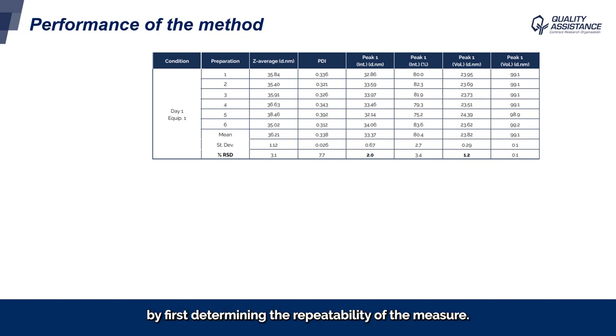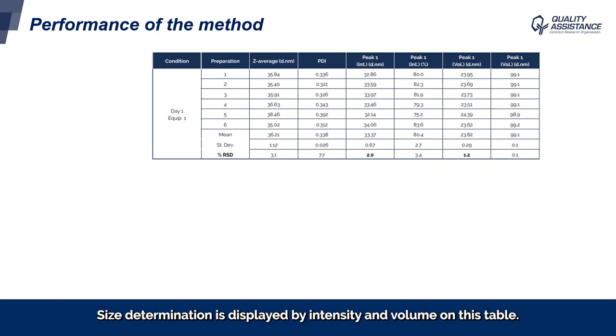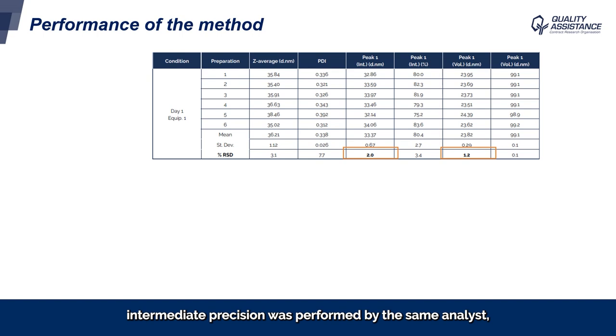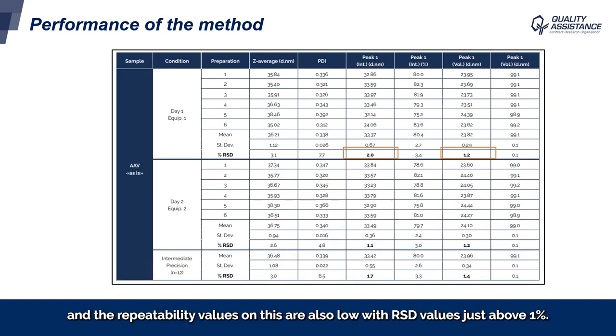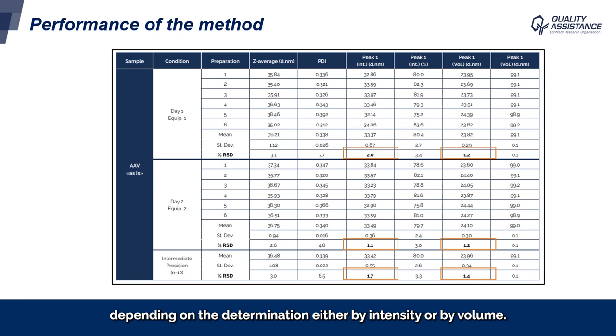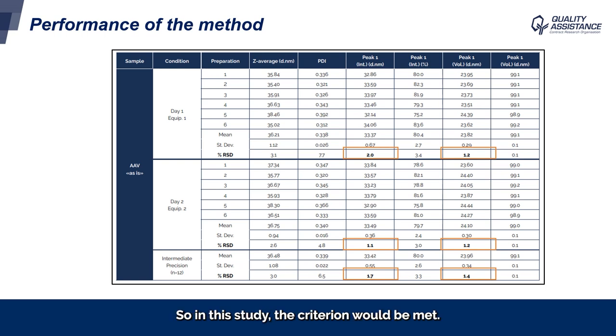Finally, we checked the performance of the method by first determining the repeatability. For one day on one equipment, the measurement was performed six times. Size determination is displayed by intensity and volume on this table. Circled in orange, we see low RSD values of 2% or 1.2% for determination by intensity or by volume. Intermediate precision was performed by the same analyst but on a second equipment and on a second day, with the measurement performed six times as well. The repeatability values are also low, with RSD values just above 1%. The intermediate precision determined from these 12 measurements also shows good results, with RSD values of 1.7% or 1.4%, depending on whether determination was by intensity or by volume. For a validation study, criteria on intermediate precision are usually set at 10%, so in this study the criterion would be met.